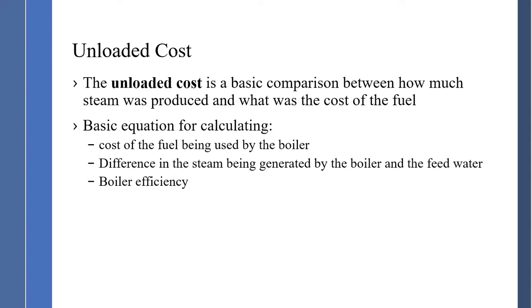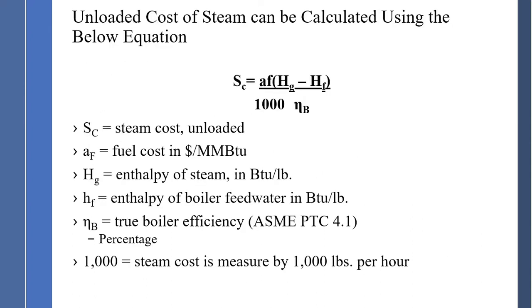The basic equation for calculating steam cost: cost of fuel being used by the boiler, difference in steam being generated and the feed water, and boiler efficiency. The calculation is: SC equals AF times (HG minus HF) divided by 1000, divided by boiler efficiency. AF is the fuel cost per million BTUs. HG is the enthalpy of steam in BTU per pound — output of the boiler. HF is the enthalpy of the boiler feed water in BTU — the water coming in from the deaerator. NB is the true boiler efficiency per ASME PTC 4.1, as a percentage. And 1000 represents the steam cost measured in 1000 pounds per hour.